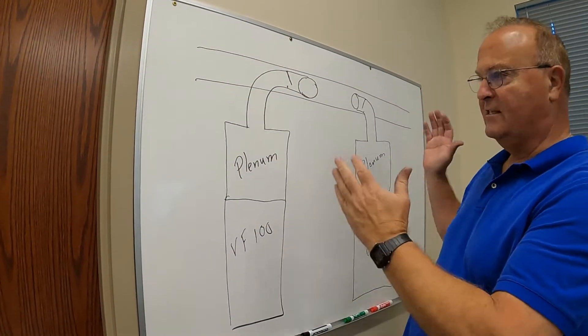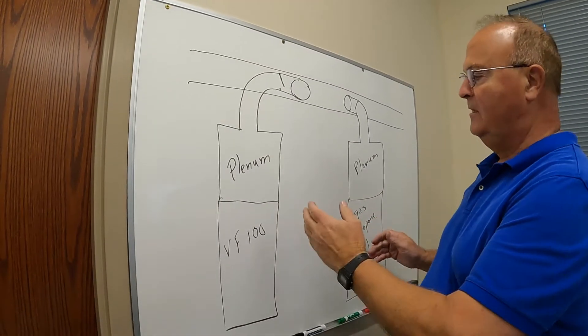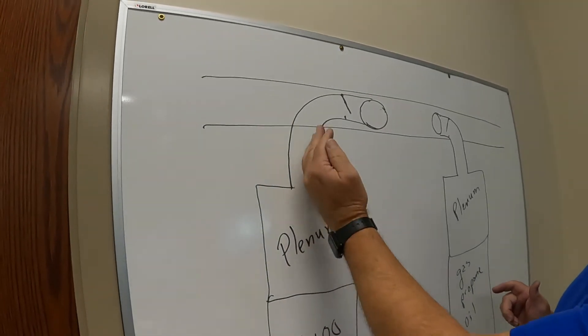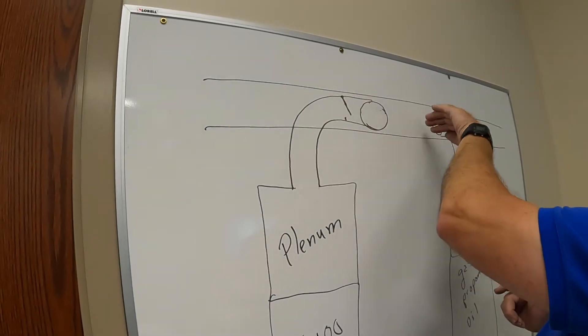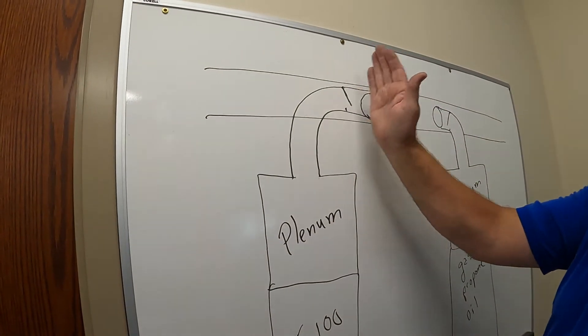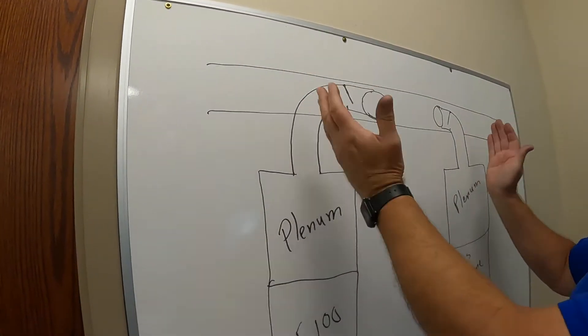One thing you're going to have to have is a backdraft flap, and that's what I'm showing right here. So the air can basically only go into the warm air trunk line. It can't come out. If it tries to come out, this flap's going to shut and it's going to block it. Both furnaces need a backdraft flap.